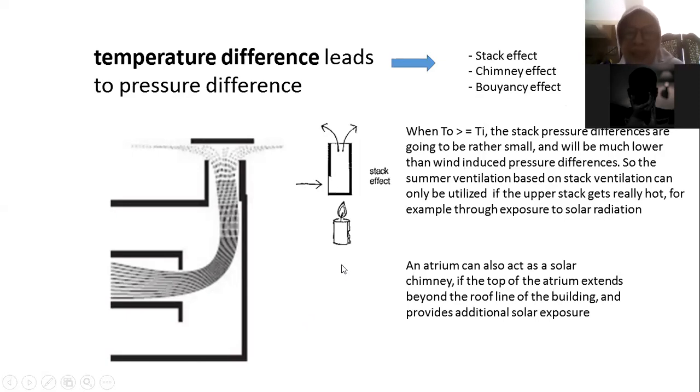When the outdoor temperature is about the same or higher than the indoor temperature, the stack pressure differences are going to be small and much lower than wind-induced pressure differences.